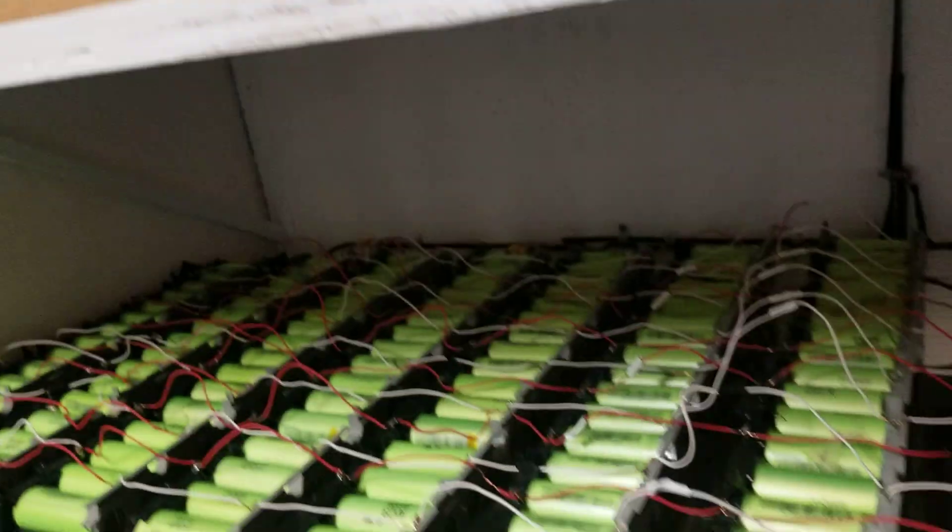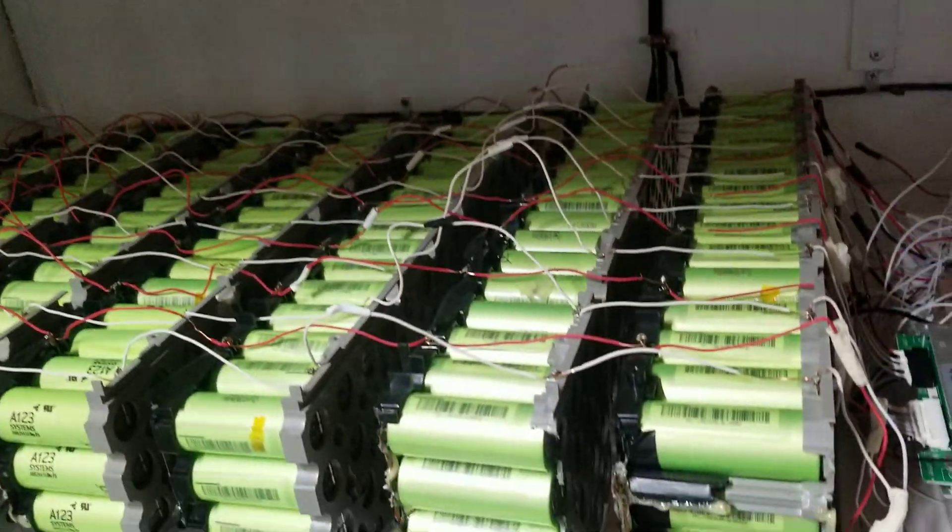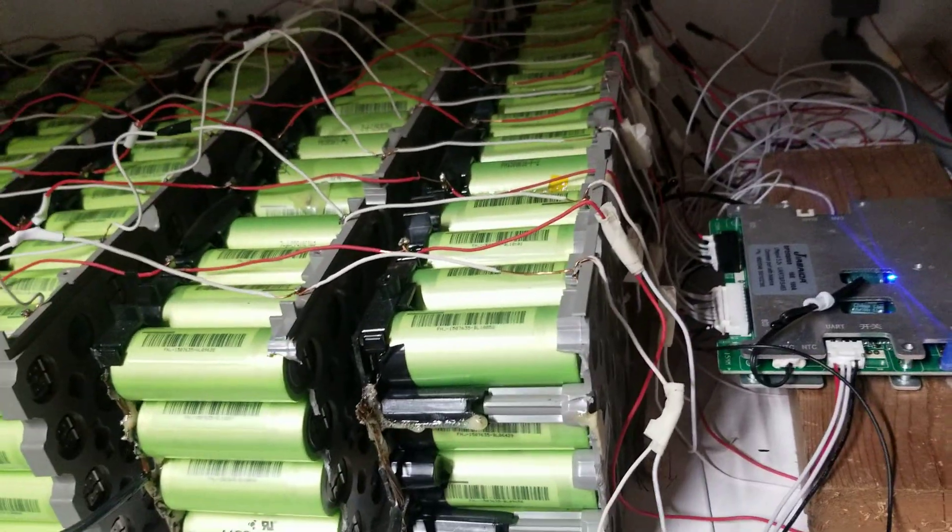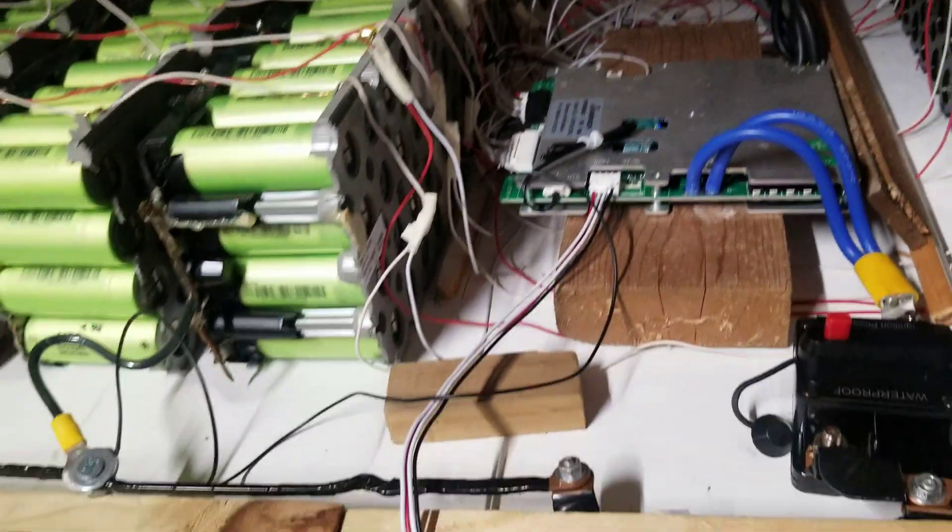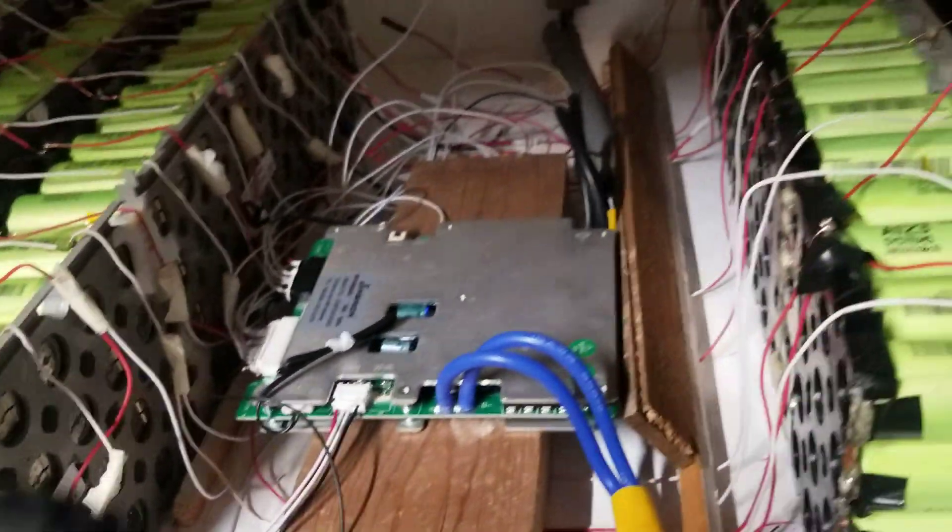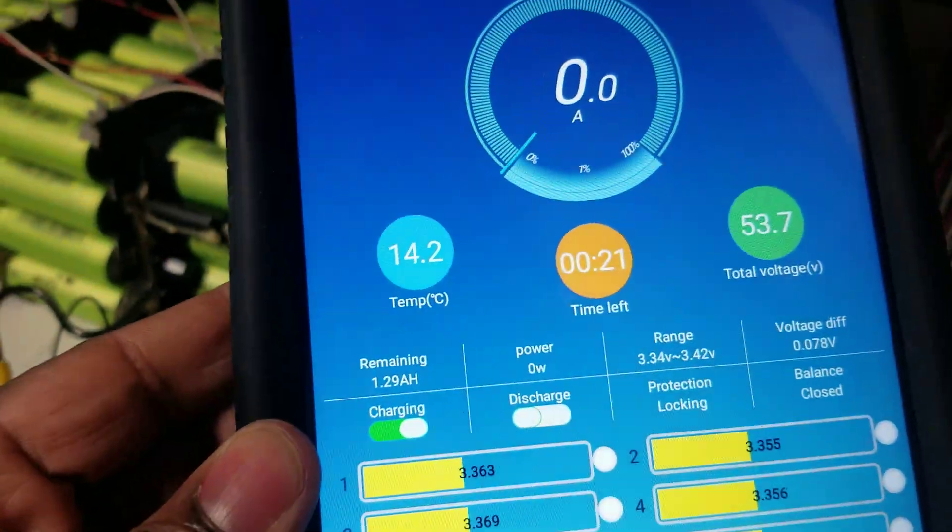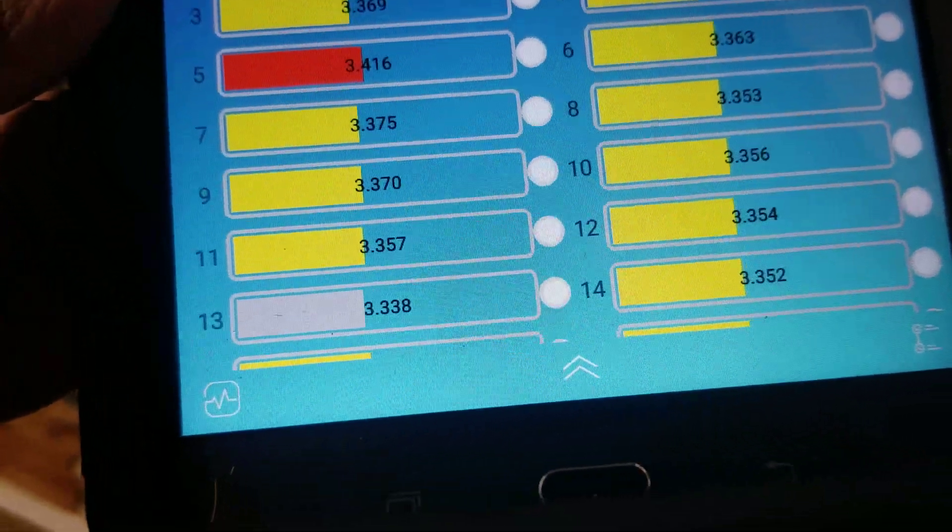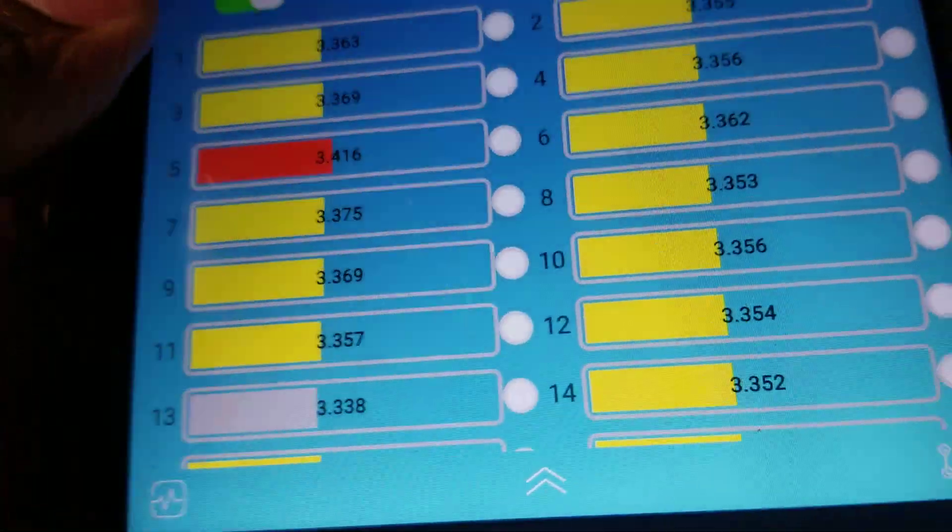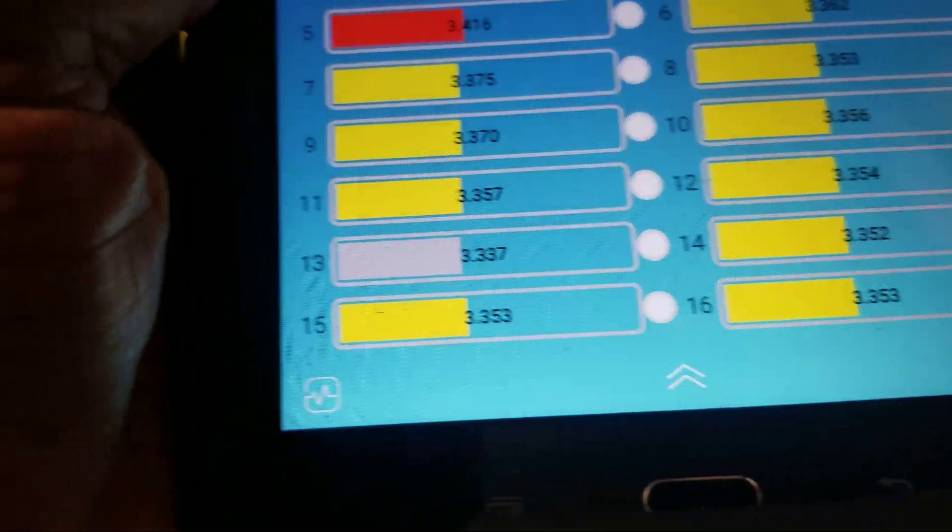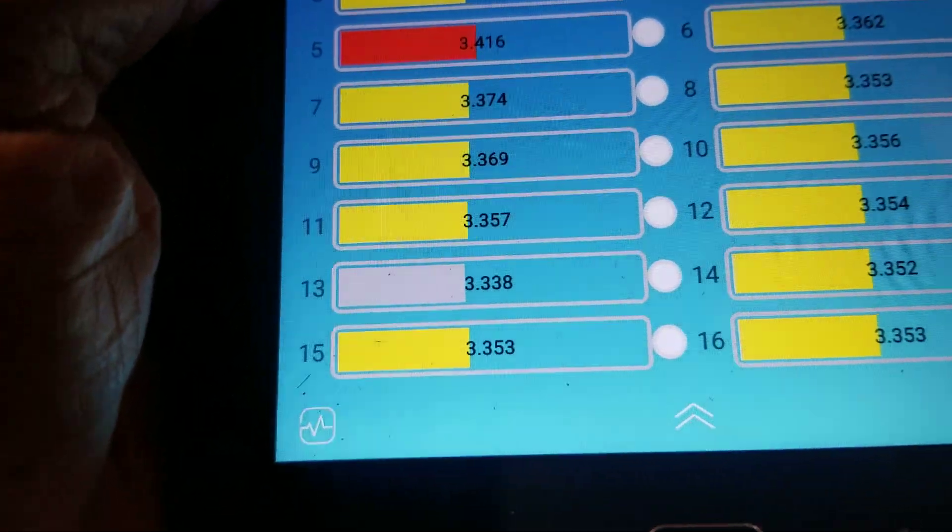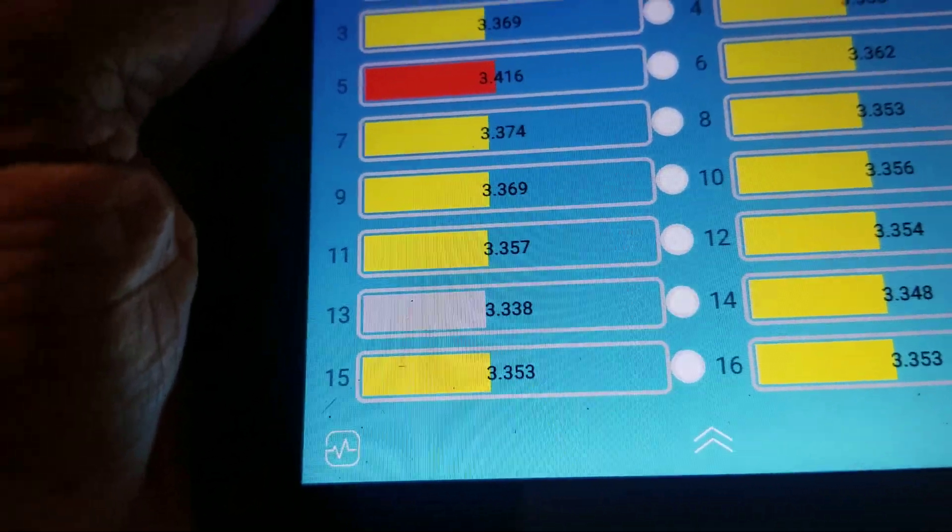What I'm going to do, right now I'm being charged. The system is being charged. So this is the system, it's being charged. I have this cell here, cell number 13. It's always giving me a hard time. It's not balanced. It's the weakest cell in there.